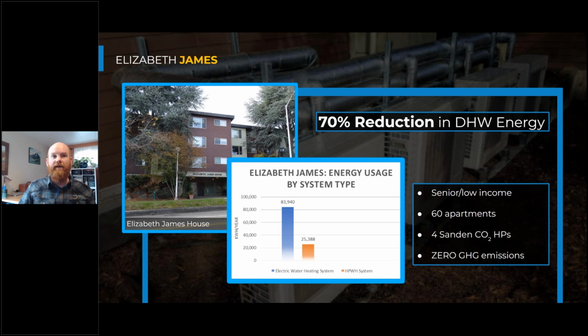And we dramatically reduced the energy use over a given year and are saving the tenants about $6,000 per year in their energy bills, which is fairly significant. So cutting that energy usage down by a factor of 3. And the CO2 heat pump water heaters are very low on that greenhouse gas emission scale. So that's another huge advantage to use that technology here. The CO2 is not limited to 40-degree ambient air temperature. So we actually located these heat pump water heaters right outside above here and piped them into the mechanical room on this basement level.